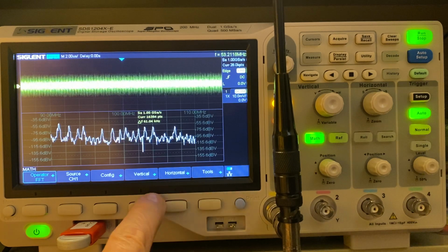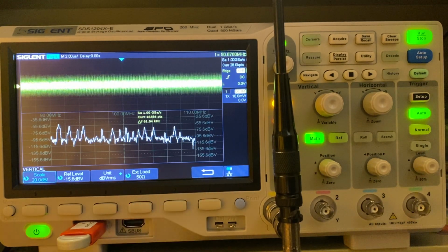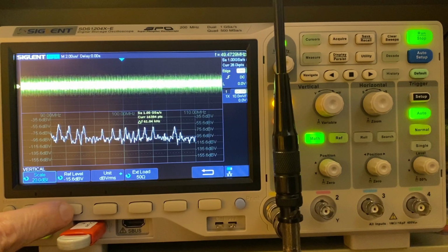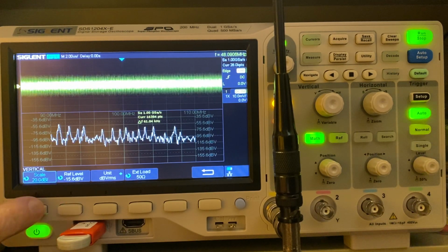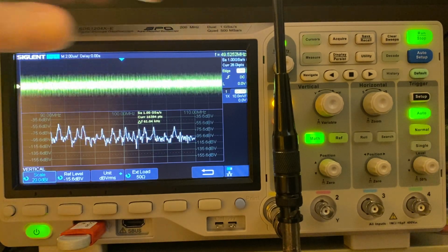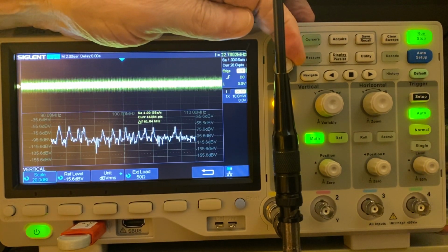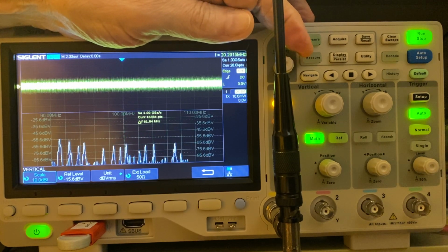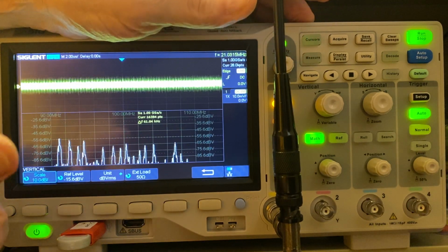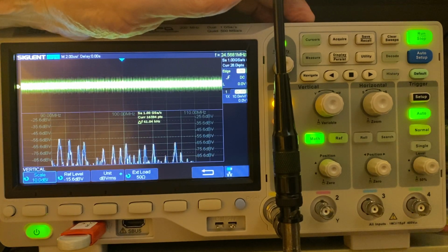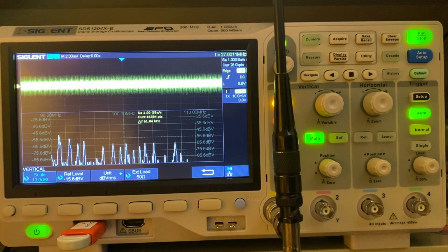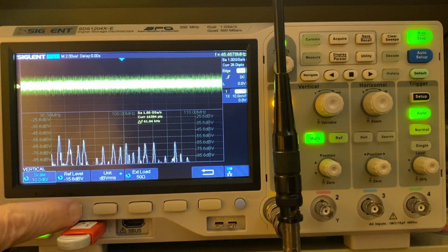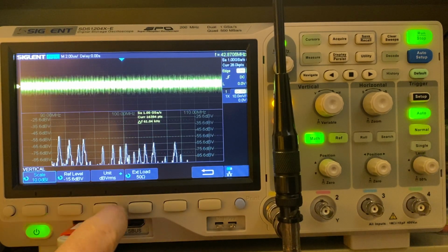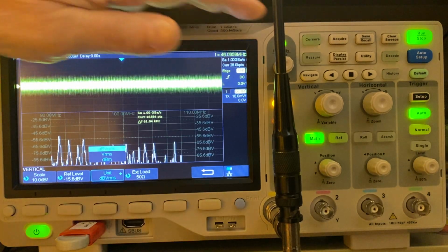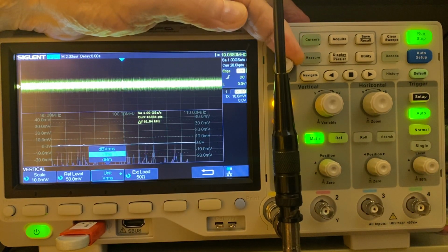If we go back and select the vertical options now, we can select some more useful settings for measurement. So I'm going to set a wider range on the scale, a wider range of display, that is to say a narrower view, by setting 10 dB per division. And I'm going to change the units to dBm, which are a more familiar unit for this kind of work.